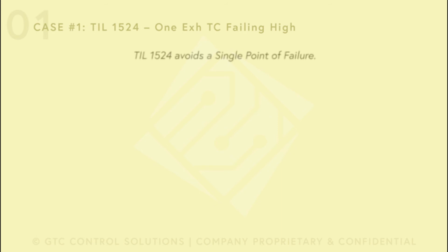We will discuss 2 TILs, TILs 1524 and 1275, and then a bonus track. 1524 deals with the case of a single point of failure, and it avoids it. Thermocouples, as we mentioned before, can fail high. And in the case of the exhaust thermocouples, one exhaust thermocouple failing high would cause a high exhaust spread trip. That's a very annoying situation.